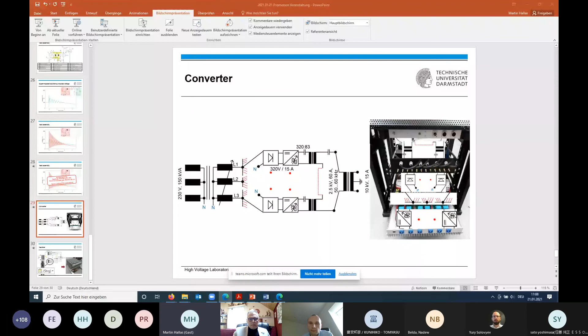Also a good question. We have investigated this in several pre-tests in our laboratory on a scaled arrangement, and we have not yet published anything from these investigations. Right now I can share that up to now the data shows oscillating impulse voltage is nearly the same stress for the insulation, for the insulator, and for the gas gap as a conventional lightning impulse. If anything, an oscillating impulse is even a more critical test, with the front times we are applying in our test facility, than a conventional lightning impulse. But as I said, further publications will be available in future on this topic.